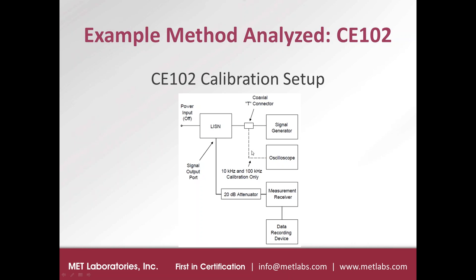And also an oscilloscope is connected with a T connector here so that we can tune or calibrate the signals at the 10 and 100 kilohertz levels. And that's because the LISN actually doesn't have a flat 50 ohm impedance all the way across its range. Below 1 megahertz and down to 10 kilohertz, the impedance actually rolls down. So there's going to be a correction factor for that. And the way that that is accounted for is by tuning the signal level by measuring the amplitude with an oscilloscope during the process.